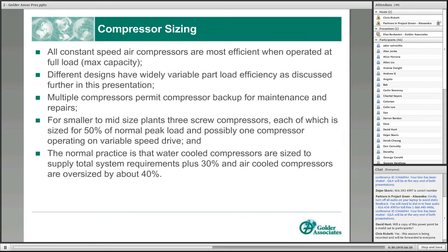Looking at compressor sizing and how we typically size the compressor plant, just a comment: most air compressors operate very efficiently at max load or full load. At part loads, no compressor is working very efficiently. So you strive to design a plant with a control system that maximizes the number of compressors running at full load and minimizes any machine running at part load. For smaller plants, you would typically add, say, a 3rd compressor. If we're sizing a plant for 2 compressors, as the following slide shows, you might have a 3rd one for redundancy to allow for breakdowns and things of that sort, allowing you to continue producing with the 2 compressors and the 3rd one in maintenance mode.